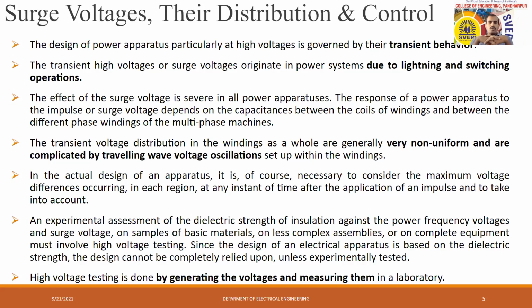All that concept should be considered whenever we think about surge voltages. Whenever we do the assessment for the dielectric strength of insulation against power frequency voltages, high voltage testing can simply be done by generating voltage and measuring it. That is a simple thing.